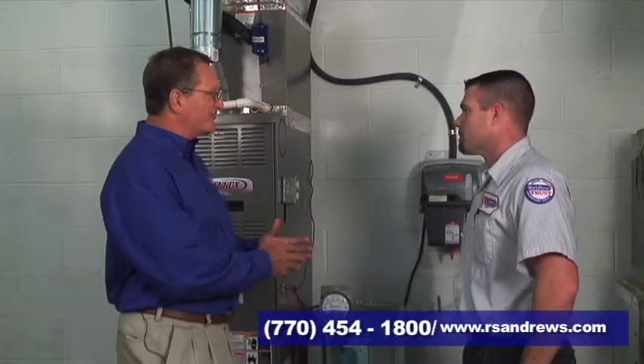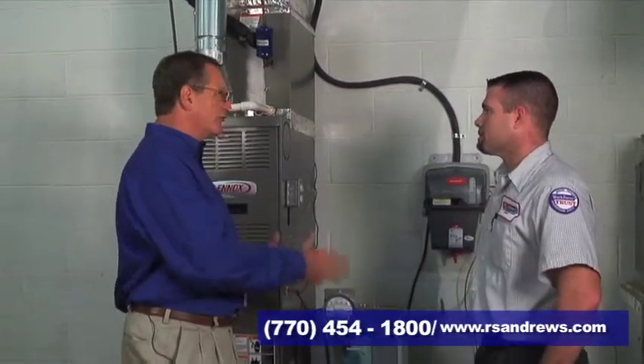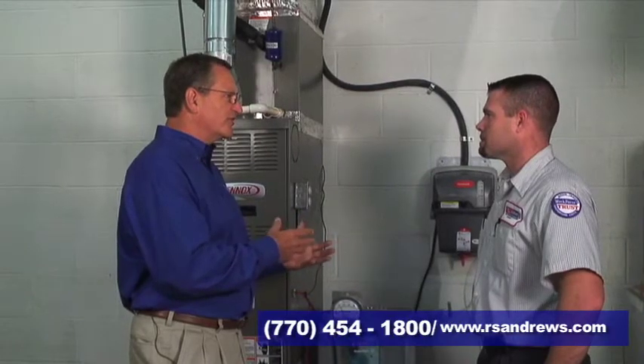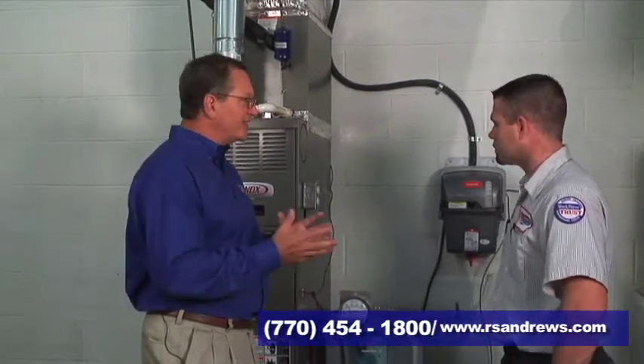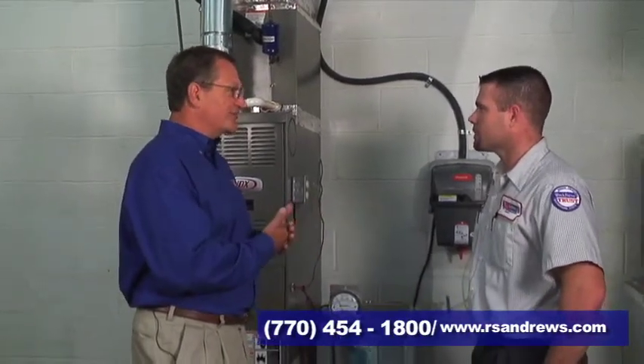So the blower's inside the furnace and it's pulling air through the house, running it through the furnace to either heat or cool the system. And then the static pressure is how much pressure that is on that motor. Is that correct? Correct. It's how hard the blower motor has to work.